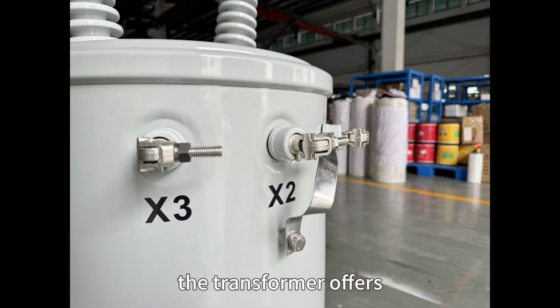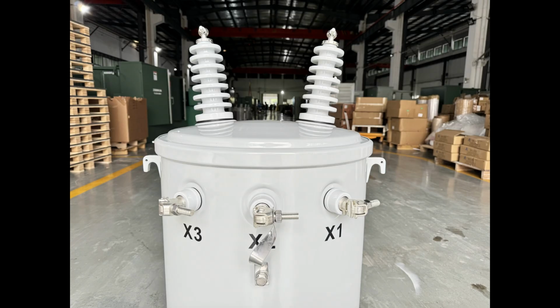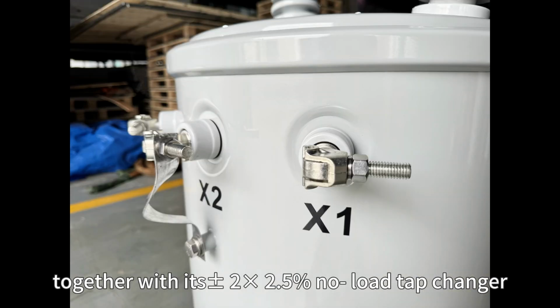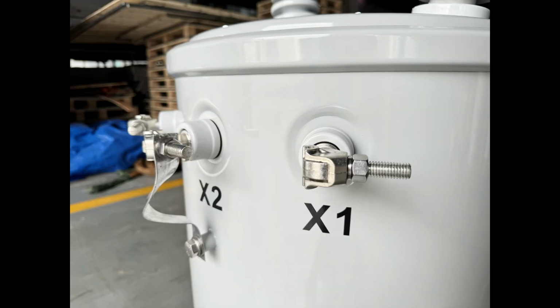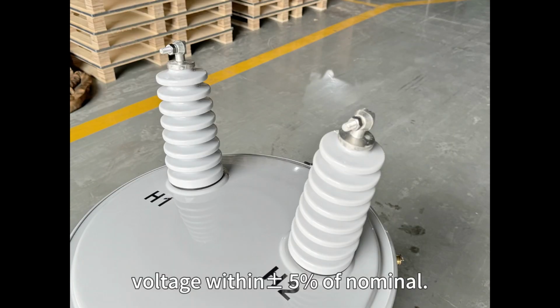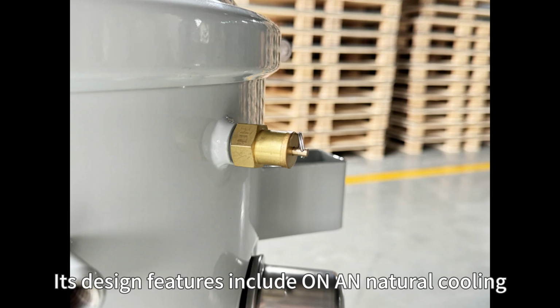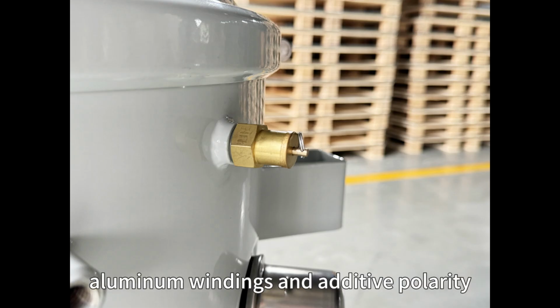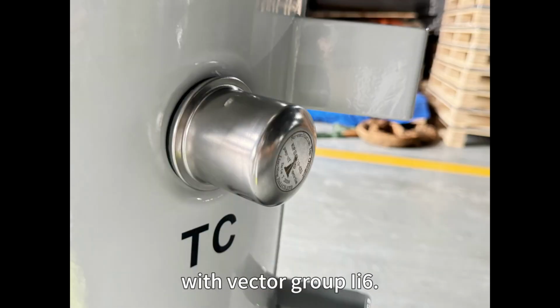The transformer offers good voltage regulation and, together with its 2 x 2.5% no-load tap changer, ensures stable secondary voltage within 5% of nominal. Its design features include ONAN natural cooling, aluminum windings, additive polarity, and vector group II6.